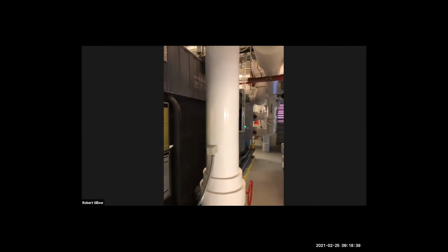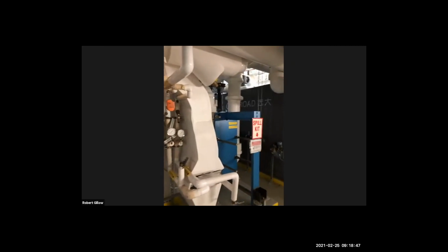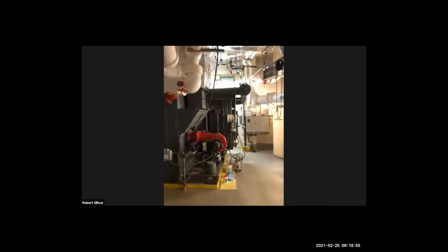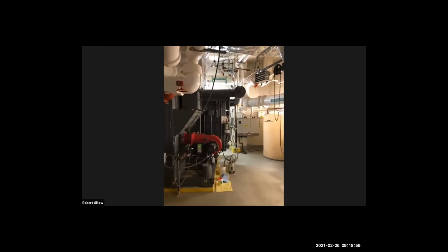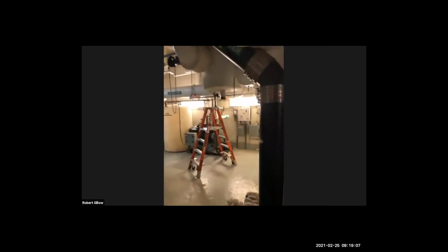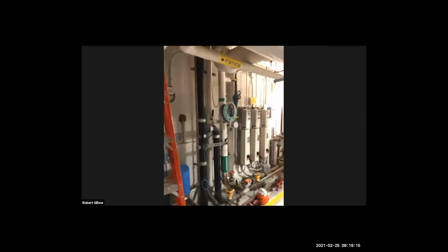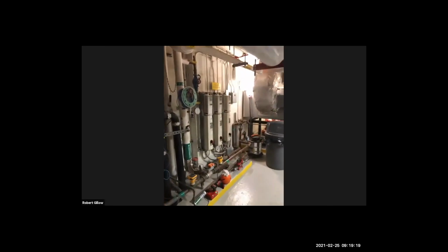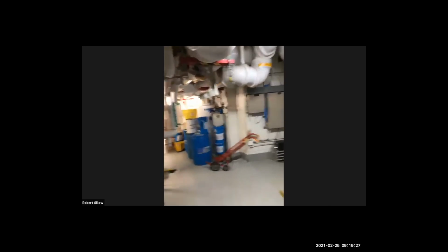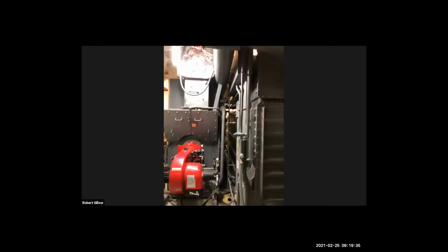And so it's a combination of chillers, heat exchangers that are part of the overall cooling tower system. And so we are feeding reclaimed water up to the cooling tower in this cooling tower system. The tower is outside. You'll see that in a second, but these are the combination of chillers and heat exchangers. And so it's really important to talk early with your cooling tower consultant, because there's various forms of cooling towers that can be used. At the Solaire here, we have a shell and tube heat exchanger. Other buildings, we have flat plate heat exchangers, and some of them are more resilient to different types of water quality. So as we're talking about this water energy nexus, and as you've heard from Mike, these connections go far beyond thermal energy recovery. We also are looking at feeding reclaimed water up into the cooling tower, and we can do that more water efficient. We can do that more energy efficient, and it's how we actually integrate these technologies together.